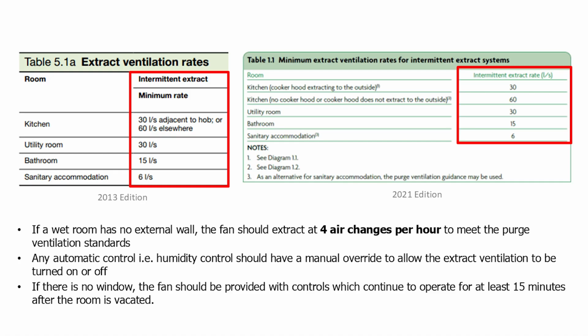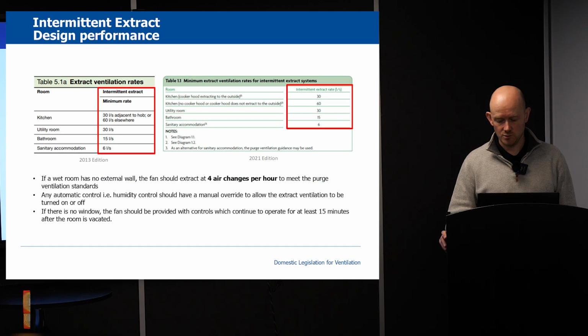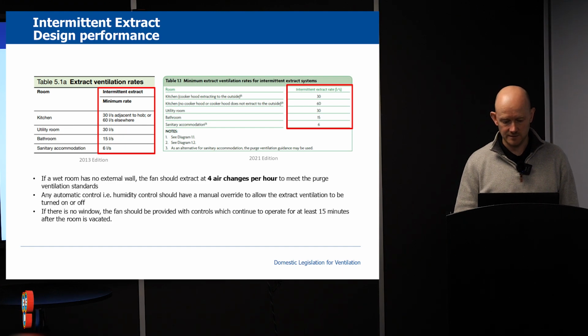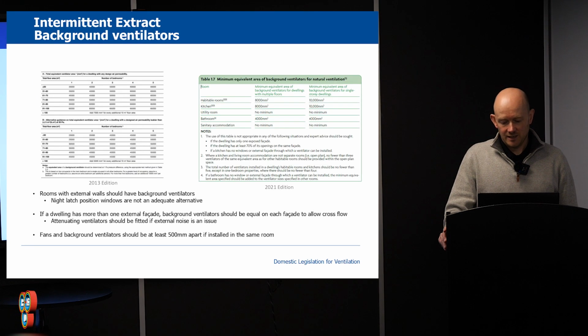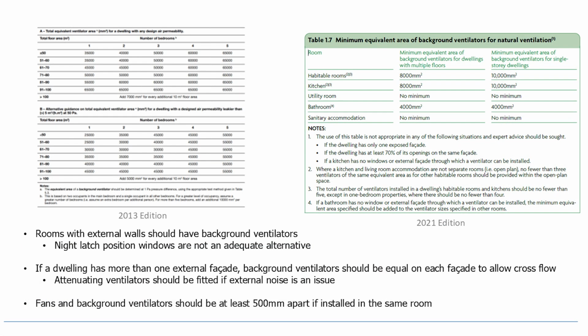An automatic control such as humidity control should have a manual override to allow occupants to turn the extract ventilation on or off. And if no window is present, the fan should be provided with controls which continue to operate for at least 15 minutes after the room is vacated. Background ventilators are now defined by single storey or multi-storey. There is a 20% increase in area for habitable rooms and a 60% increase in area for kitchens. Fans and background ventilators should be at least 500 mm apart if installed in the same room. And if any external facade faces an area of sustained and loud noise, an attenuating background ventilator is needed.